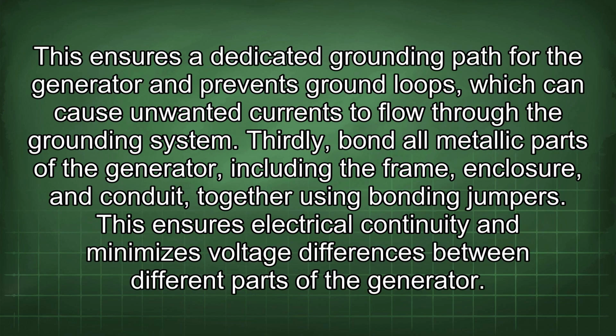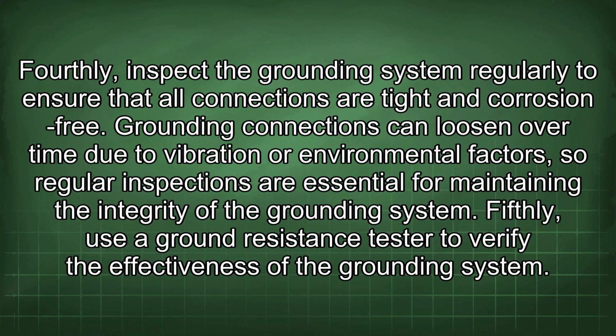This ensures a dedicated grounding path for the generator and prevents ground loops, which can cause unwanted currents to flow through the grounding system. Thirdly, bond all metallic parts of the generator, including the frame, enclosure, and conduit, together using bonding jumpers. This ensures electrical continuity and minimizes voltage differences between different parts of the generator. Fourthly, inspect the grounding system regularly to ensure that all connections are tight and corrosion-free.